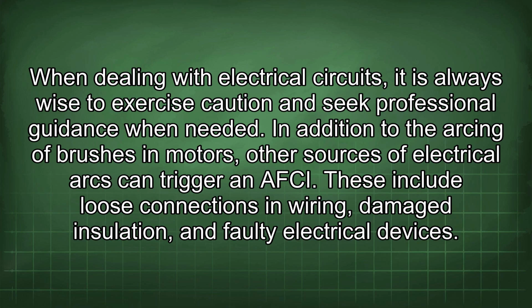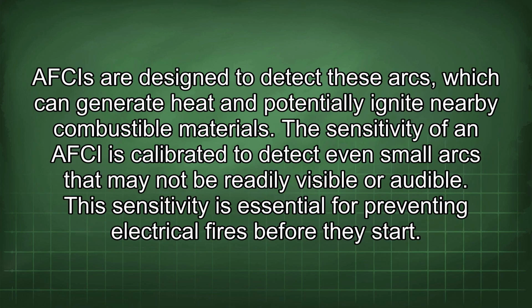In addition to the arcing of brushes in motors, other sources of electrical arcs can trigger an AFCI. These include loose connections in wiring, damaged insulation, and faulty electrical devices. AFCIs are designed to detect these arcs, which can generate heat and potentially ignite nearby combustible materials. The sensitivity of an AFCI is calibrated to detect even small arcs that may not be readily visible or audible. This sensitivity is essential for preventing electrical fires before they start.